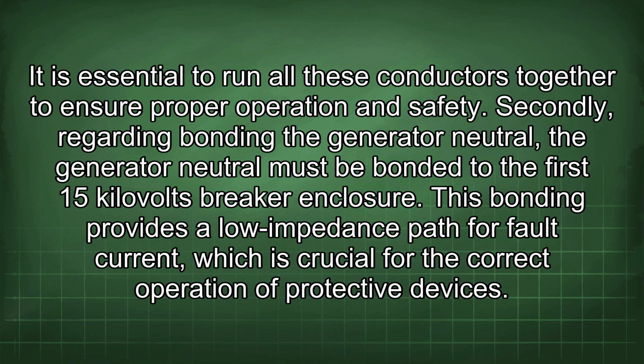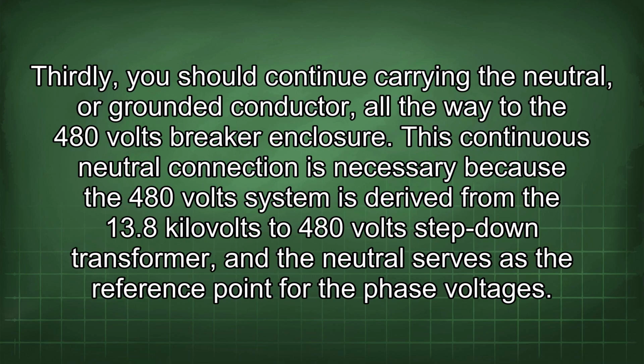Secondly, regarding bonding, the generator neutral must be bonded to the first 15 kilovolts breaker enclosure. This bonding provides a low impedance path for fault current, which is crucial for the correct operation of protective devices. Thirdly, you should continue carrying the neutral or grounded conductor all the way to the 480 volts breaker enclosure. This continuous neutral connection is necessary because the 480 volts system is derived from the 13.8 kilovolts to 480 volts step-down transformer, and the neutral serves as the reference point for the phase voltages.